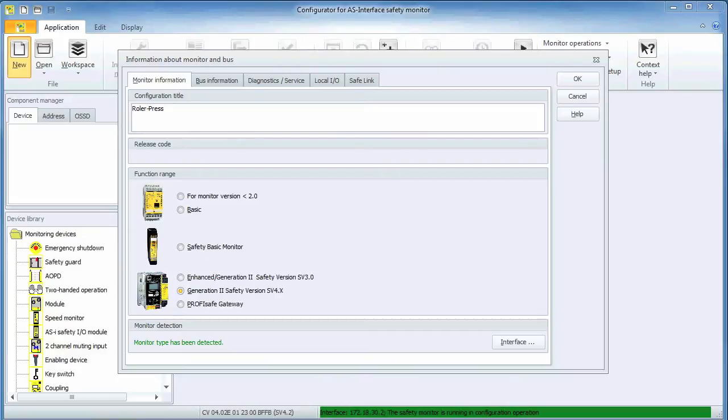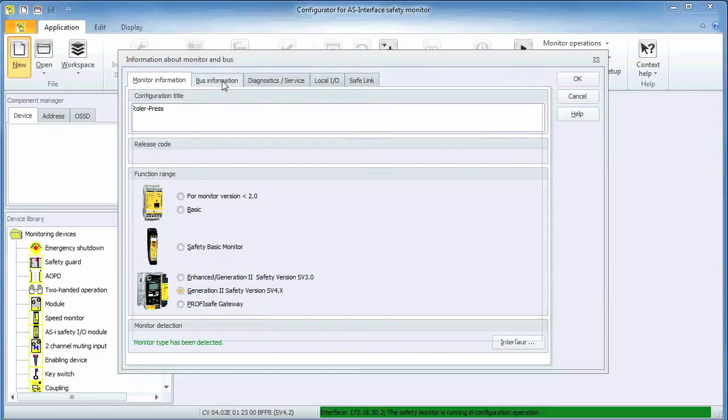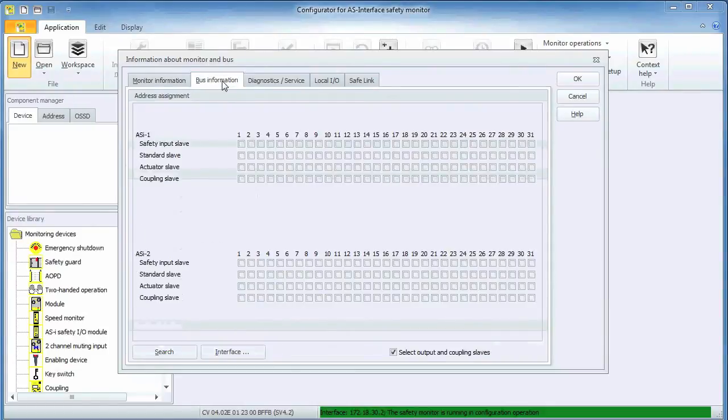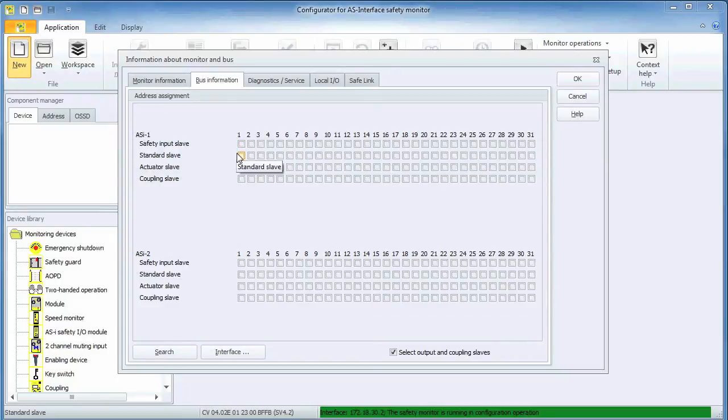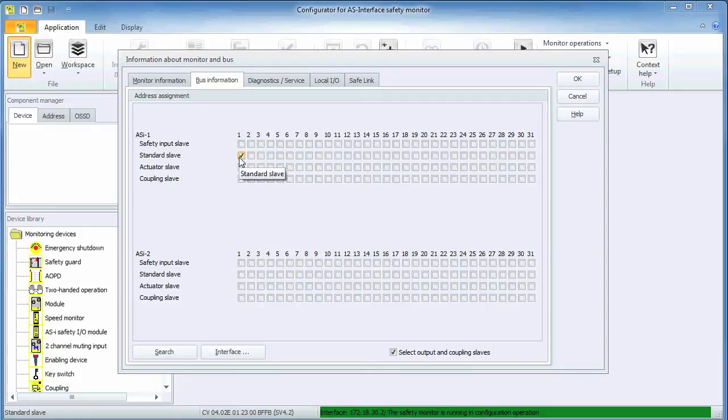Clicking the bus information tab brings up the screen identifying the addresses of the AS interface modules we are using. This does not assign addresses to modules on the network. That is usually done with a handheld, but reserves them within Simon Plus. 1A is the diagnostics address I assigned to the safety encoder module earlier using the handheld. If you need to see how this is done, consider watching our video on this topic.